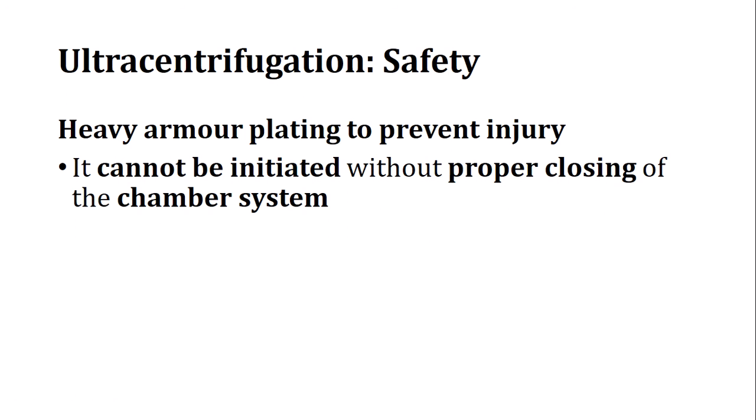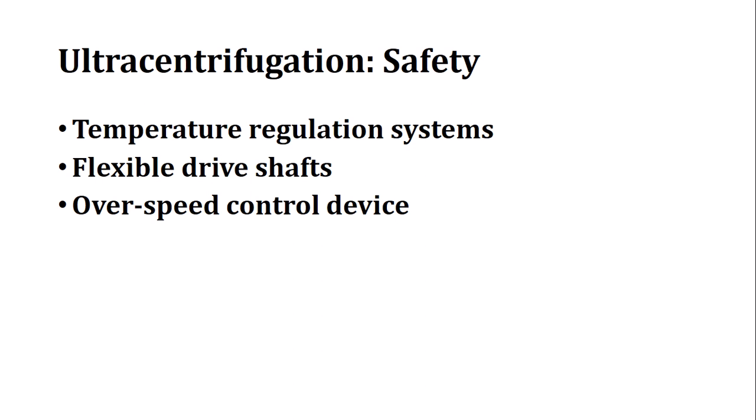Regarding safety aspects for the ultracentrifuge: it has heavy armor plating to prevent injury, which cannot be broken even in the event of a device failure. It cannot be initiated without proper closing of the chamber system. There is a fine temperature regulation system, and there is a flexible drive shaft — if there is any imbalance, instead of breaking, the shaft can bend, helping to prevent accidents.